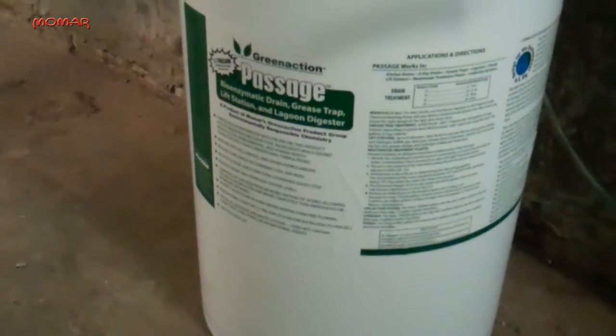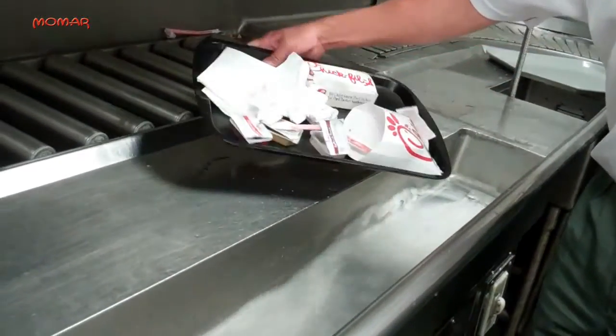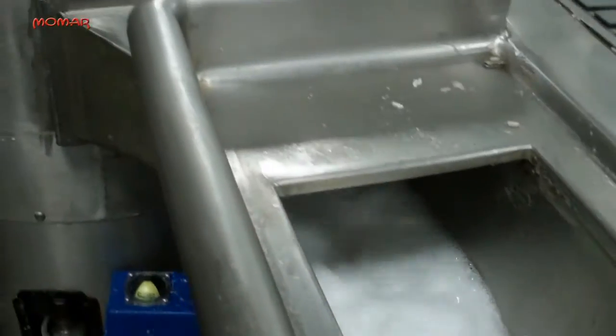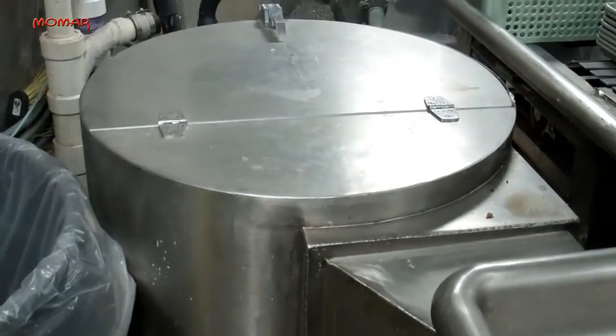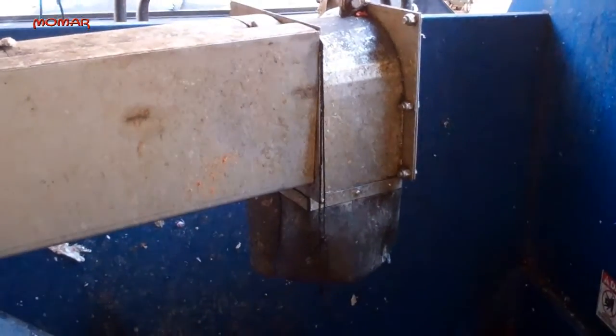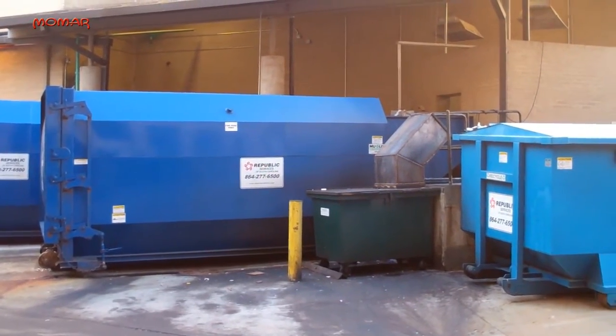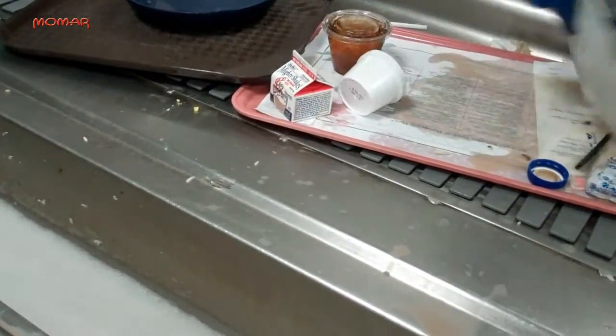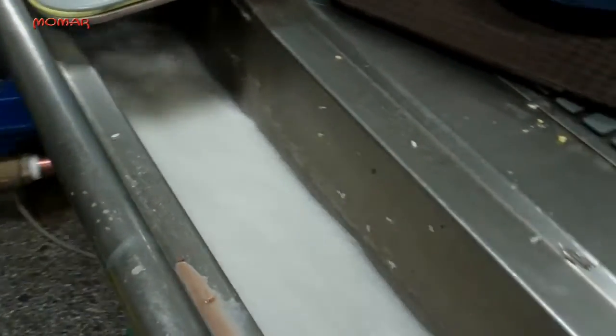One of the more unusual and more critical applications in the hospital is this unique solid waste processor located in the two main hospital kitchens. In each, waste material of all sorts is fed into a water trough and carried into a stainless steel pulper and cutter, where the waste is literally pulped into a semi-liquid slurry, piped through a water press, and fed into these waste receptacles. The system reduces human handling of waste, in turn saving labor dollars, and because it returns 95% of the water to the system, it reduces 88% of the overall volume of waste.